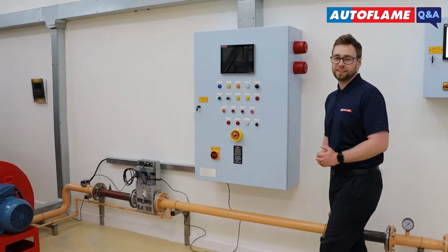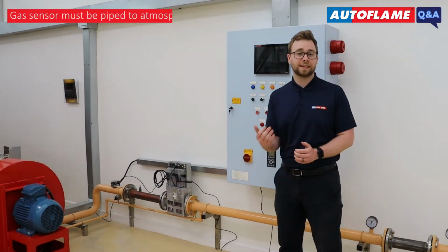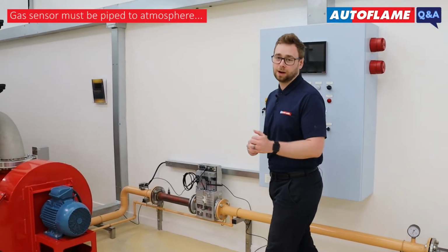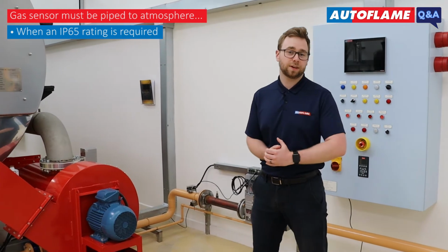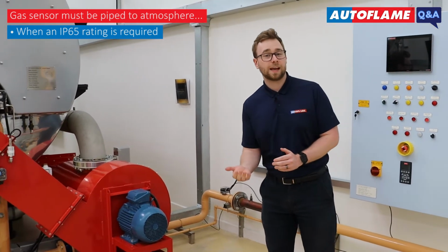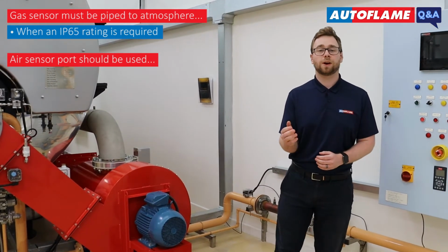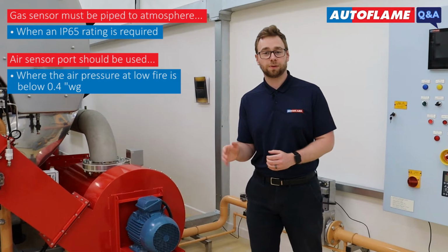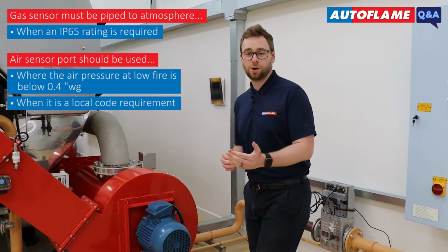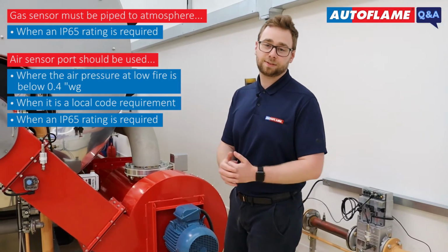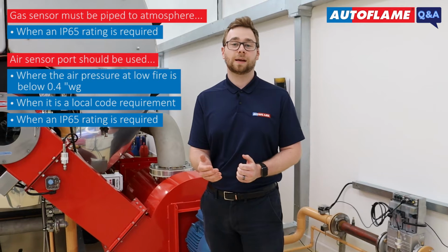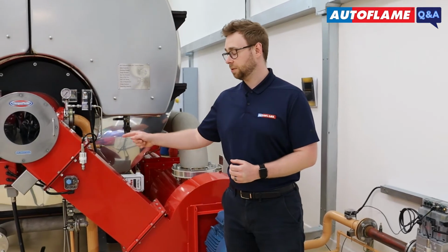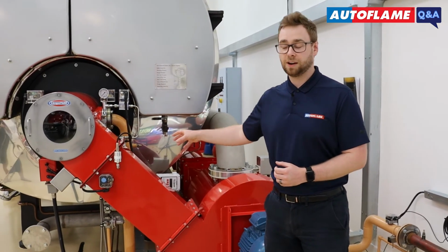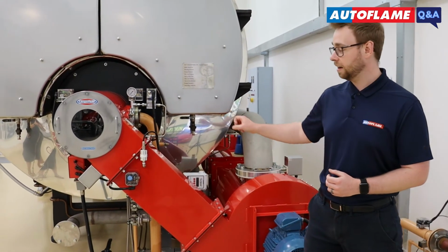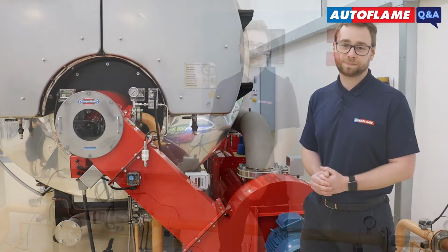Both sensors feature a differential pressure port. In the case of the gas pressure sensor, this port must be piped to atmosphere when an IP65 rating is required. In the case of the air pressure sensor, this must be used when your air pressure at low fire is below 0.4 inches water gauge, when it's a local code requirement, or when an IP65 rating is required for outside applications. You can see here on the burner that the air pressure sensor is mounted after your combustion air fan and before your air damper.